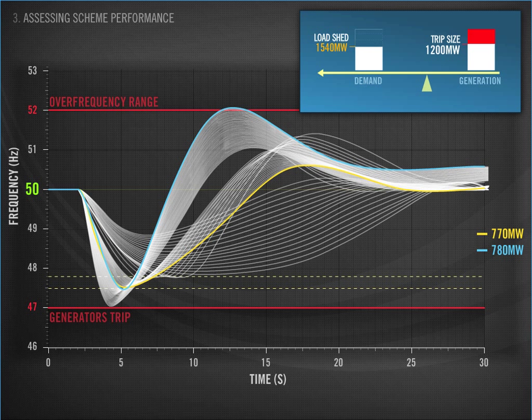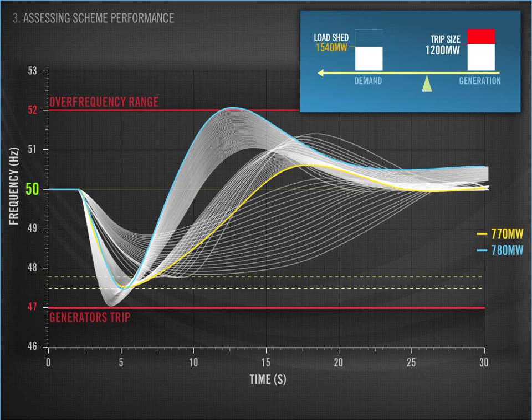As the size of generation loss increases, the amount of over-shed decreases and the frequency stays within the desired range. This analysis gives us an overview of how the scheme performs over a range of results. It enables us to see when we are shedding too much and sending the frequency higher than 52 Hz, and it also gives us a picture of how the UFLS scheme performs for larger events, such as a 1200 MW loss.